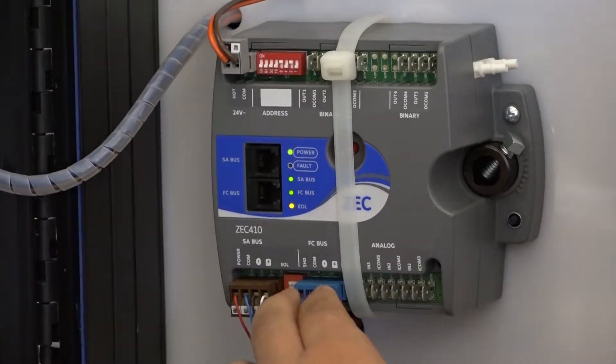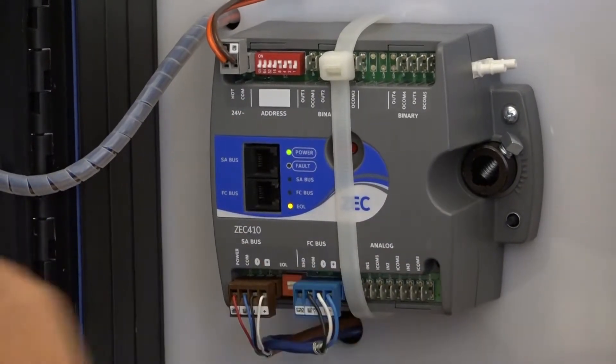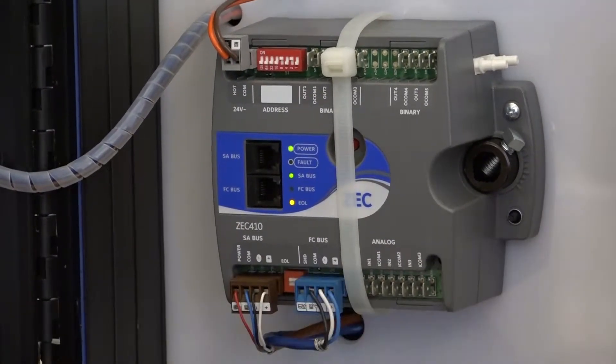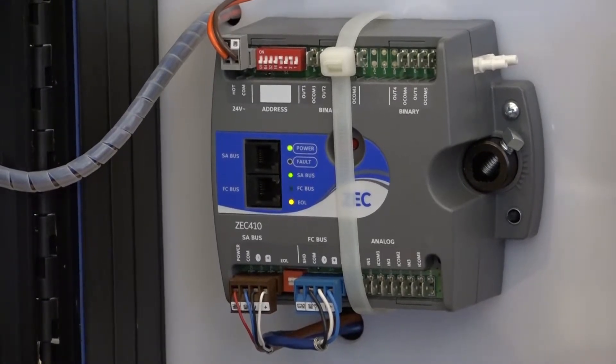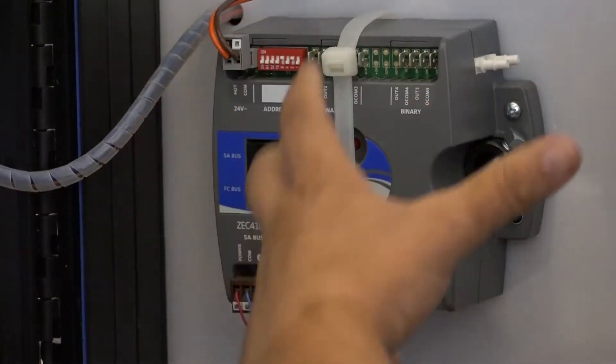These controllers wire up to that zone bus and only that zone bus. It does not wire to the system controller and they specifically wire to the zone bus of the system that is delivering the air to the box or to the dampers.